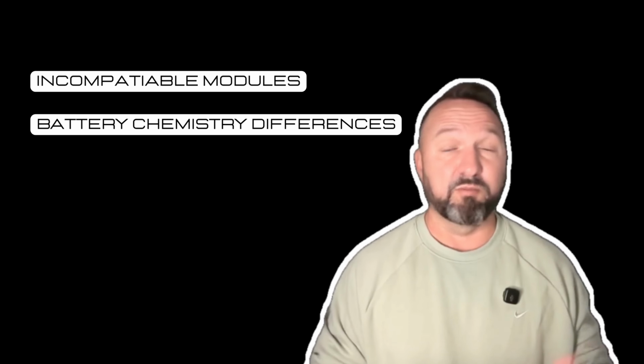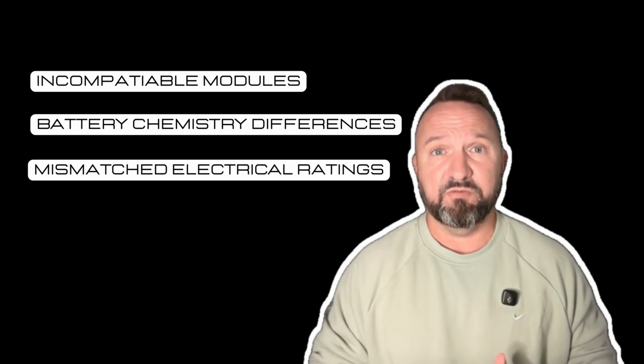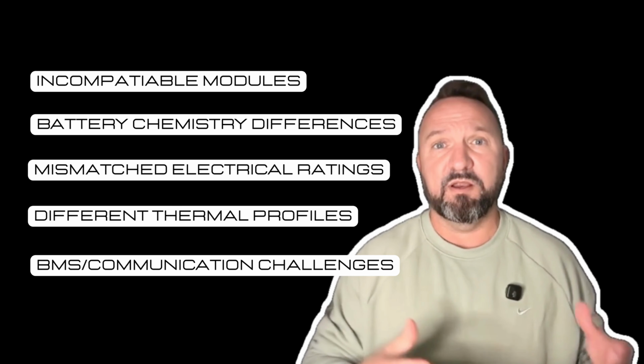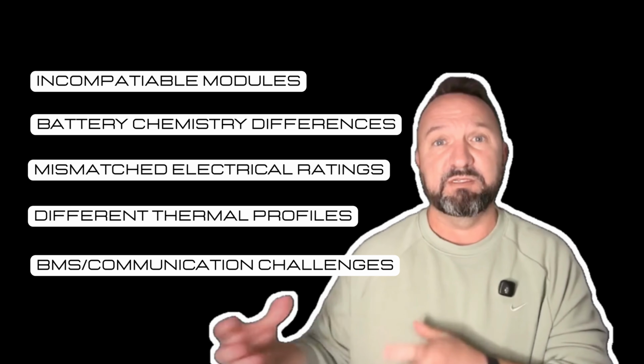Now, battery energy storage is evolving quickly, and these systems face additional challenges, really with the chemistry evolution. Manufacturers are constantly improving the cell battery design, which means older modules eventually become unavailable. What happens then? Well, operators face incompatible battery modules, different voltage profiles, different thermal characteristics, different communication profiles, and it just means this isn't a simple, let's go replace a battery module. Now we have to re-engineer the system to accept new or replacement battery modules. Oftentimes, this is called augmentation.